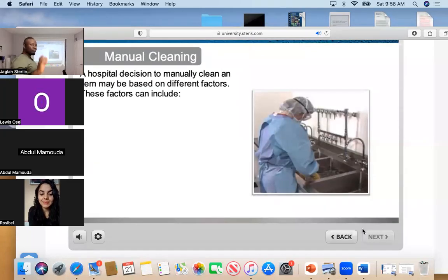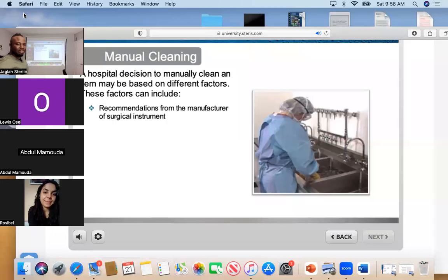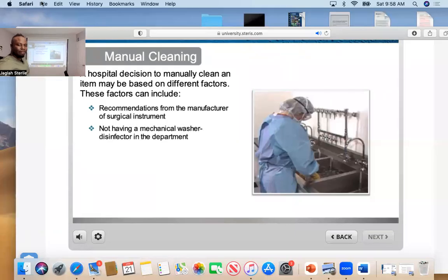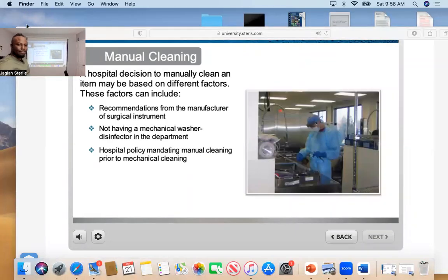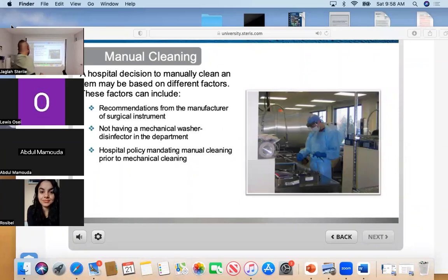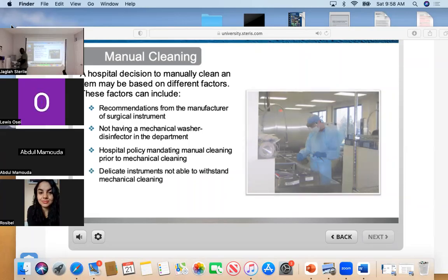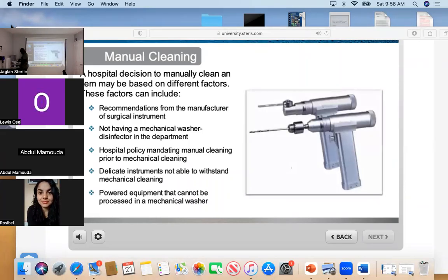A hospital's decision to manually clean an item may be based on different factors. These factors can include recommendations from the manufacturer of the surgical instrument, not having a mechanical system in the department, manually cleaning prior to the mechanical process, delicate instruments not able to withstand mechanical cleaning, or powered equipment that cannot be processed in a mechanical washer. Okay. Power equipment.